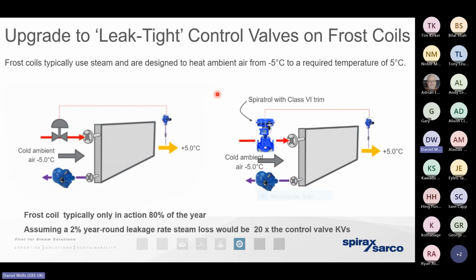If we've got a control valve that's oversized and operating very, very close to its seat, then we expect a little bit of erosion. So if we've got a low pressure, low temperature application, it could be a frost coil on an air handling unit, for example. Any steam that is passing on to the frost coil and condensing could potentially result in a problem with the condensate flooding the frost coil. And if it were to remain there, then that condensate is going to freeze. And it's going to create quite an expensive failure of that frost coil.